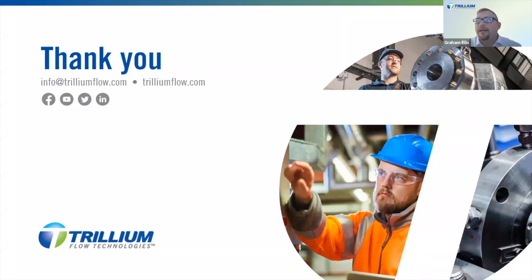Okay, thank you. And the last question that we have is, from a maintenance point, how easy and how often should the packings be changed? As you have seen, we have tested this valve for 2000 cycles, and we went up to 4000 cycles, and we did not see any major issues. But again, it is a test we did at a certain design condition. So it depends on the valve used in a particular set of conditions, on a different plant, infrastructure, and things like that. On a normal term, we recommend that after every 2 years the valve be serviced, or if you follow the Trillium recommended service and maintenance guidelines, then the packing should last longer, and it gives the same valve performance.